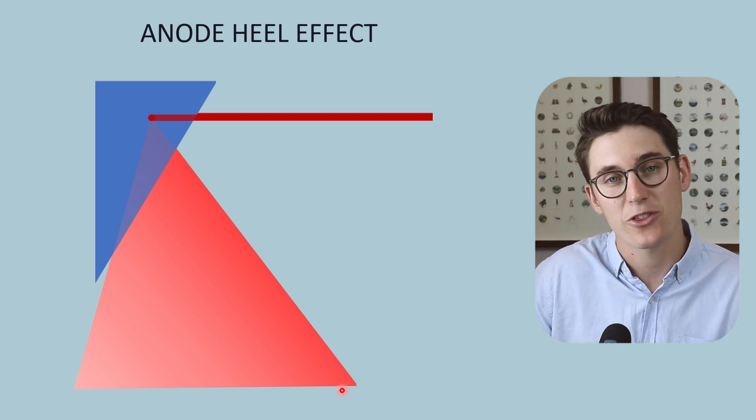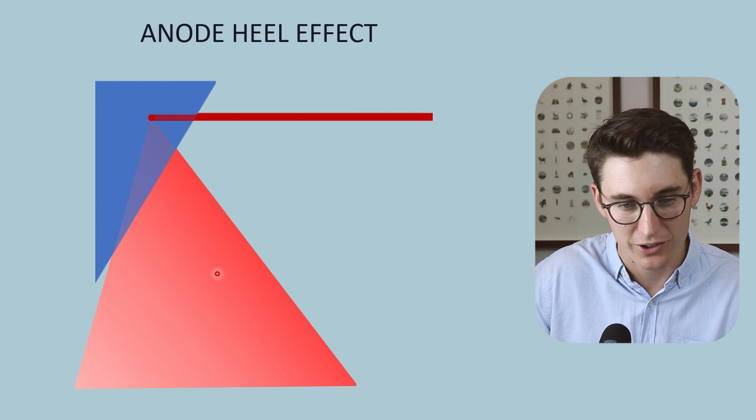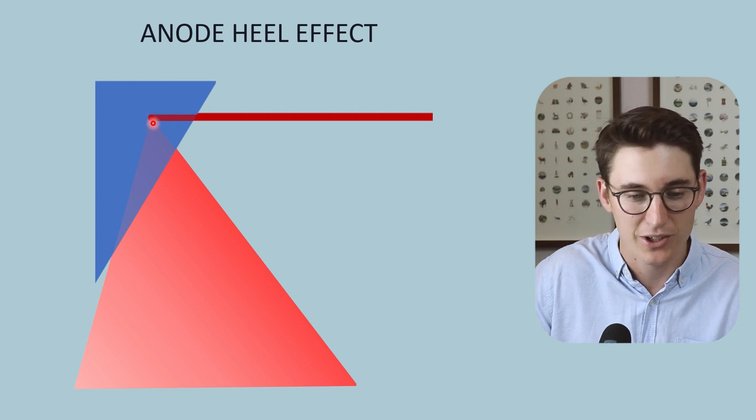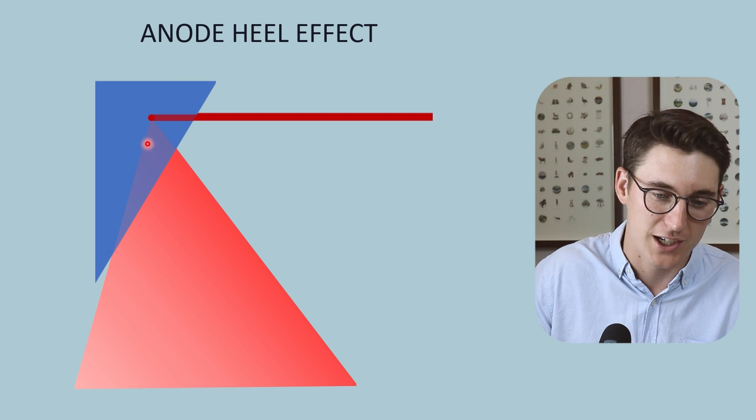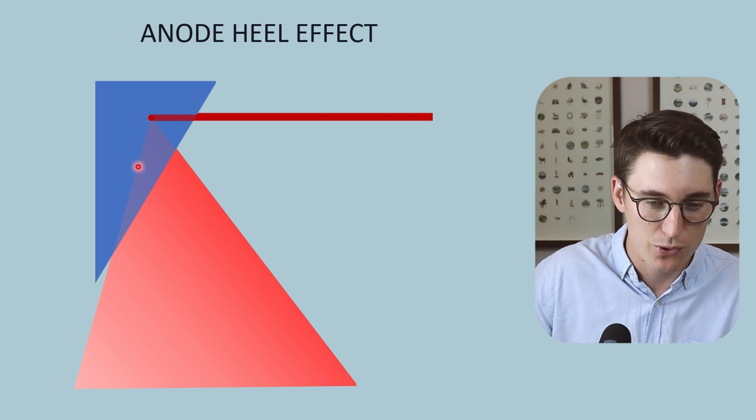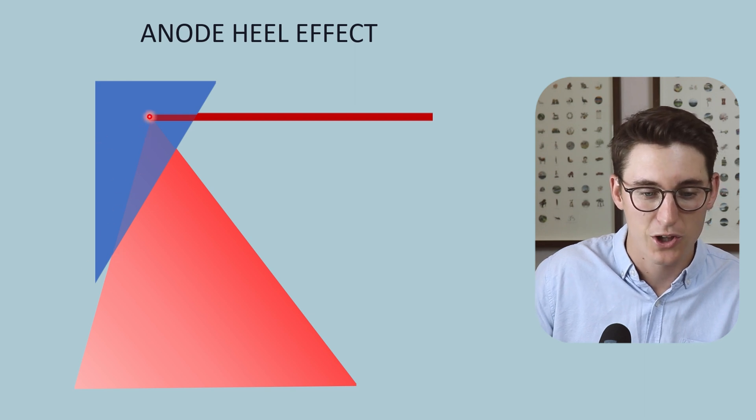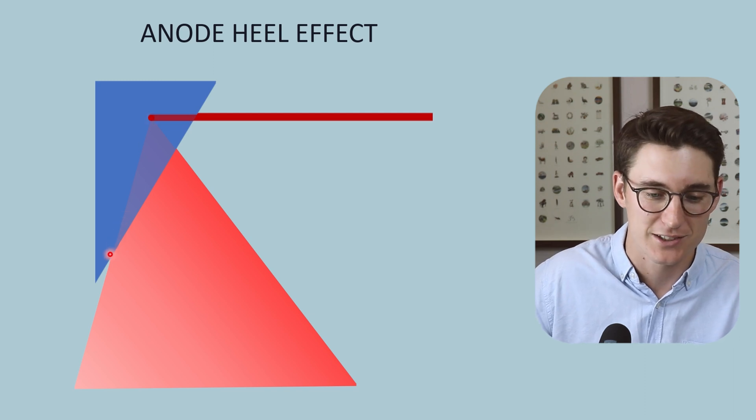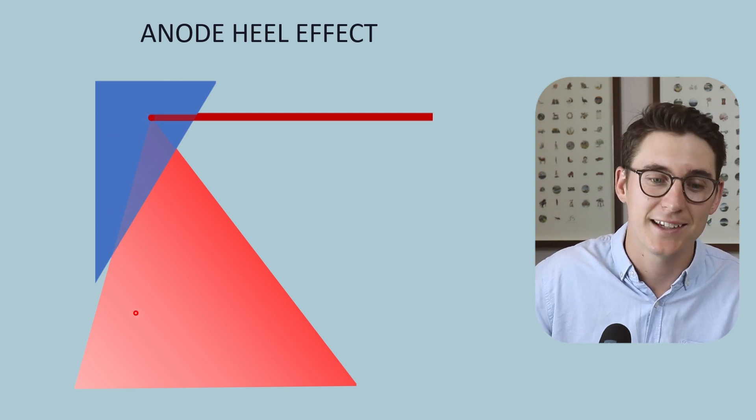Now a proportion of those x-rays will head out towards our patient. Those x-rays on the cathode side of our x-ray field have to travel through a relatively shorter distance of the anode than those on the anode side of our x-ray beam field. Now those that travel through the heel of our anode, this area here is called the heel of our anode, will be attenuated more because they have to travel through a further distance. And that's why this is called the heel effect.